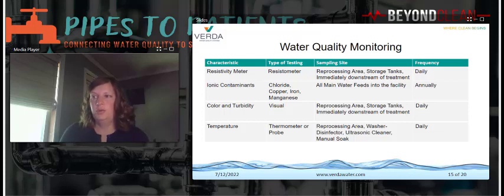In addition to the recommended monthly, quarterly, or annual testing, there is also daily testing and monitoring that is required. For example, the resistivity reading on any DI tank system is recommended to be monitored continuously, with an audible and visible alarm when the resistivity drops below 1 megohm, to prevent the inadvertent release of captured contaminants back into the water supply from the depleted DI tank.